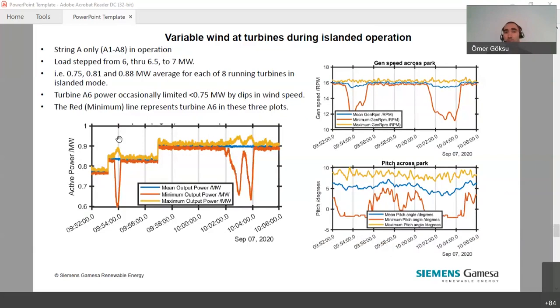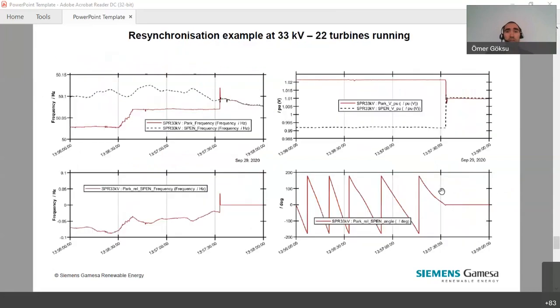And yeah, the response was quite good, you can see. One thing to note, one of the turbines, A6 here, was observing low wind. So it's actually the one, the red line here, which is showing the minimum. But the average, the blue one, is quite good, we can say. And the generator speed of that turbine is also the one showing lower here. You can see the response of the pitch, the maximum and minimum pitch in these 8 turbines and the average one. And then there was a resynchronization after islanding from the main grid, or many of them, but here we see one example.